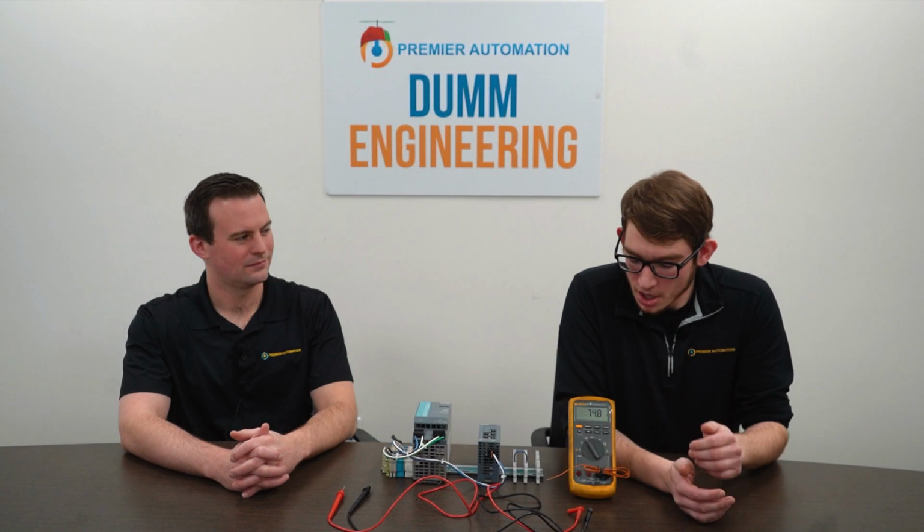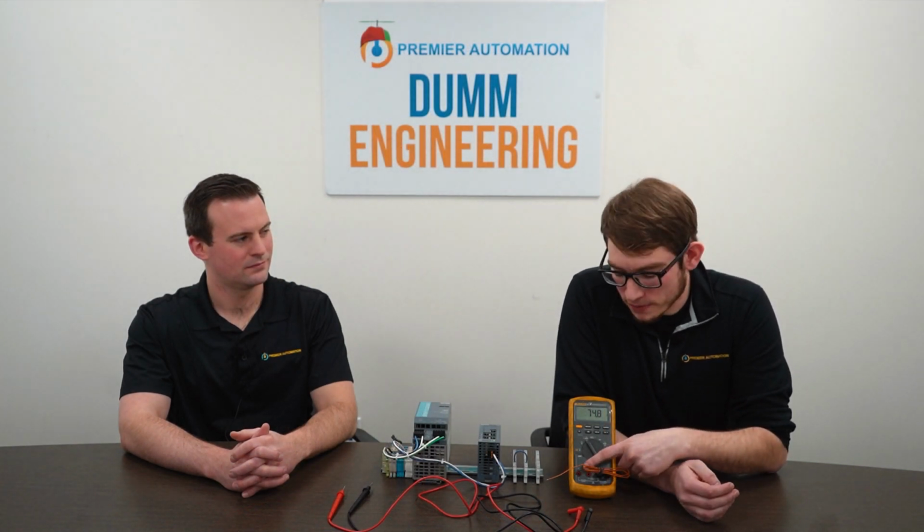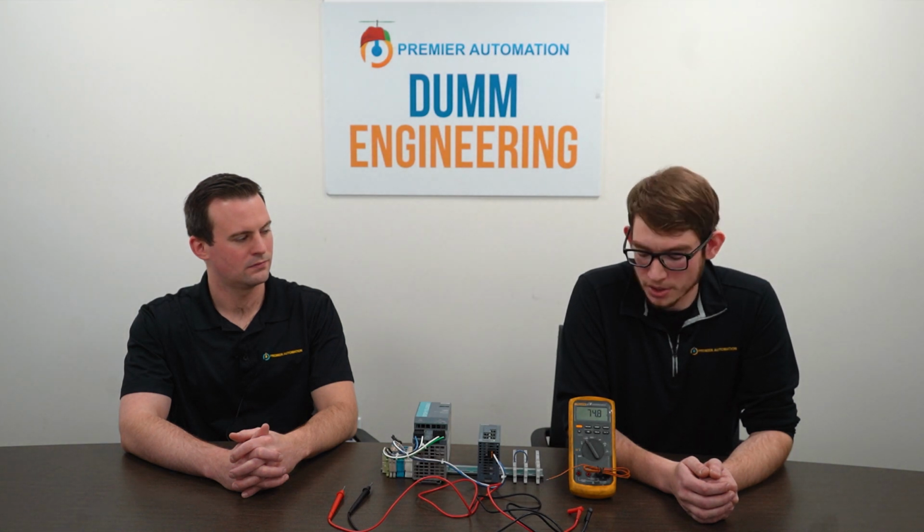With this meter, it has two different fuses in it, one for amps and one for milliamps and microamps. That way we ensure there's proper protection based on what we're reading per how we selected it on here. It's also always important when using a meter to verify your units. Some things like voltage will change the units based on their magnitude, but other ones like current, you have to actually select between a couple options. If you don't have the right one, if you measure something really small, you might just get 0 on your meter. And it's also important to remember not to blow your fuses or to check that they aren't blown in the future if you suddenly have problems measuring current.